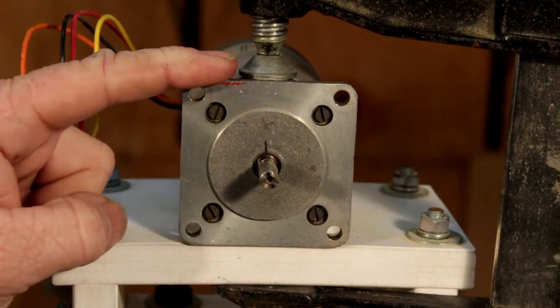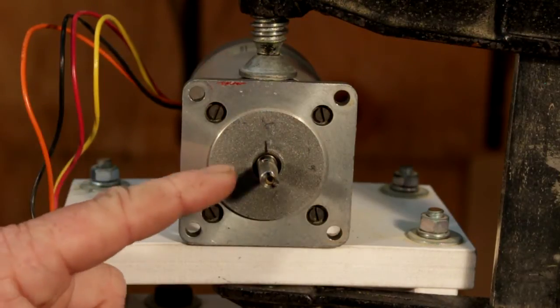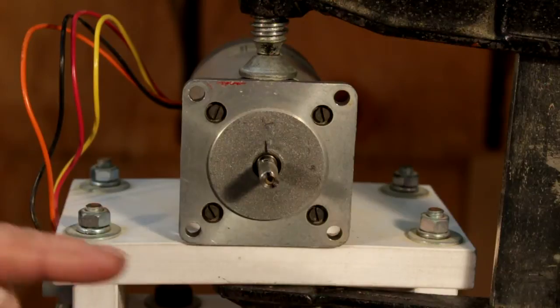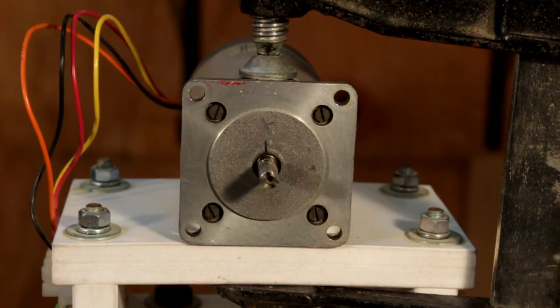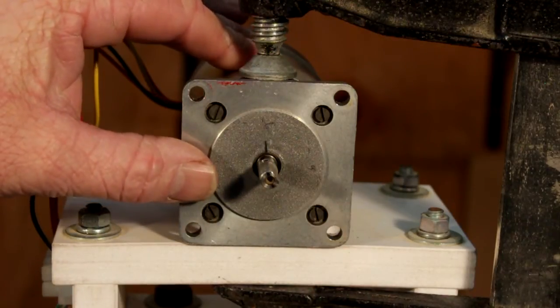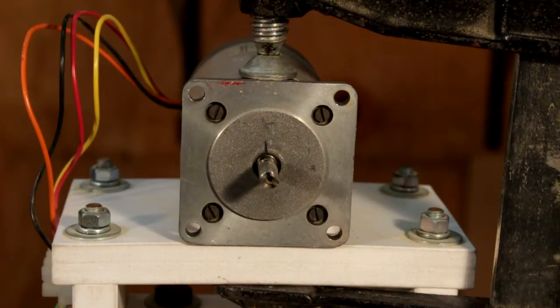It doesn't mean there isn't still a mechanical issue, but I can clearly see there is an issue here before we get to the mechanical. And when it comes to fault finding, you must always work on the assumption you've only got one problem at a time. Fix that, then move on. So I need to fix this issue first before I move on, put it back together, and retest it again with the mechanicals attached.